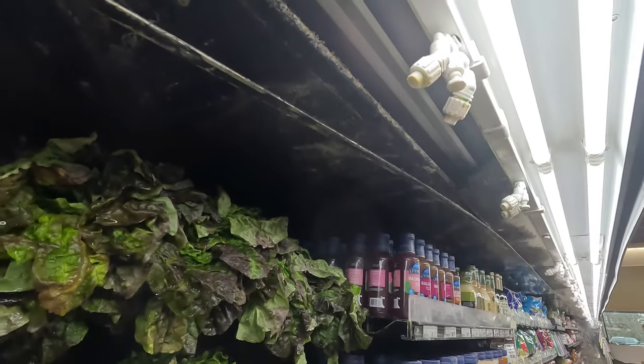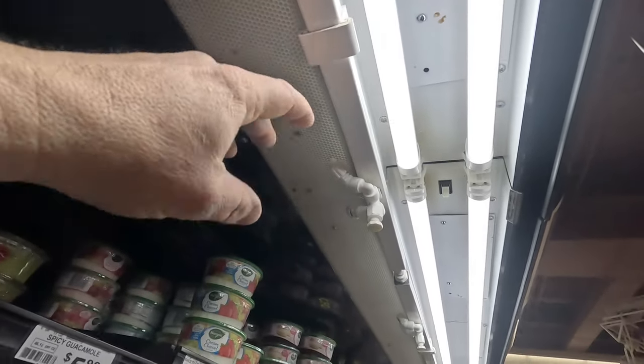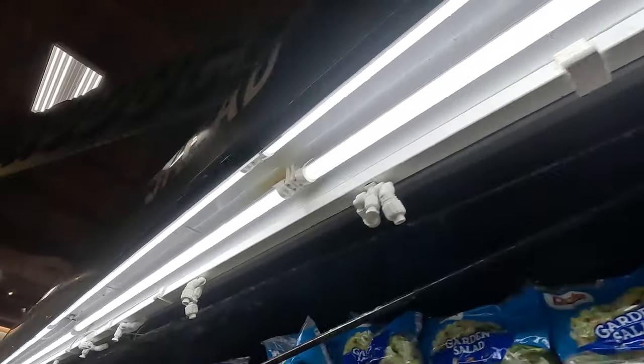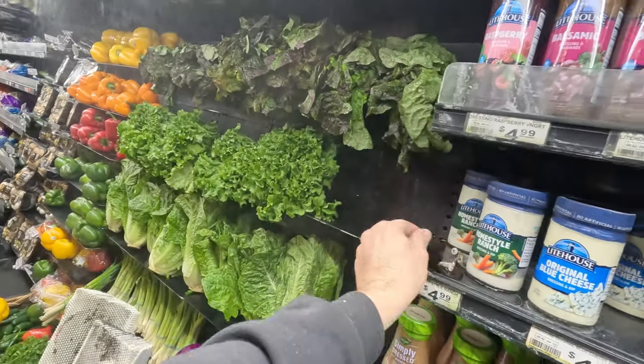It's some nasty stuff. We're going to go ahead and get it cleaned out. These last ones here, you can tell they've been shut down for quite a while. The spray nozzles are galling out of them, and it's not really that dirty. It actually looks pretty white, so we've got quite a good chunk out of there. We're going to put some screws back up here so this isn't dangling down. Moisture is our biggest issue here.